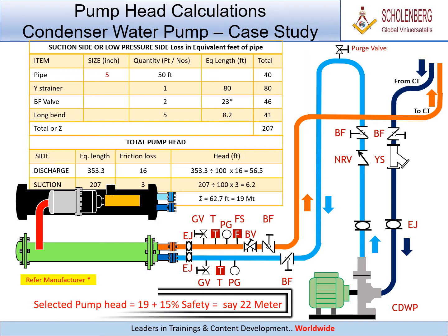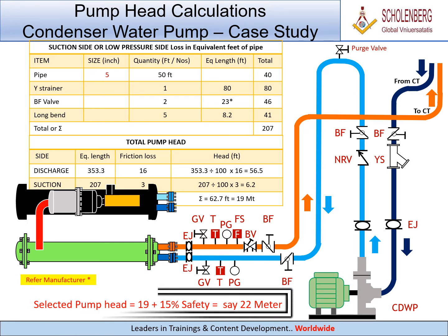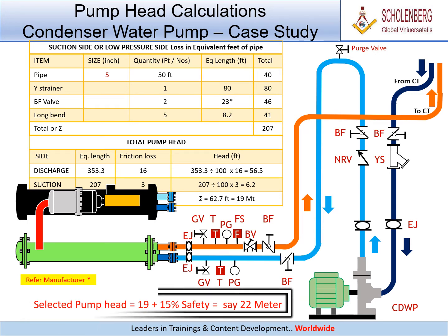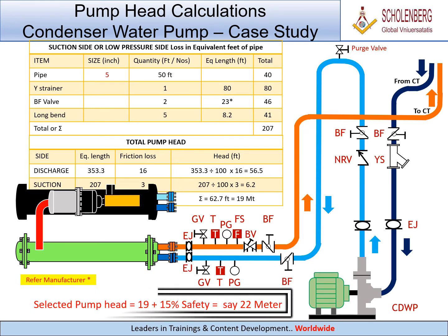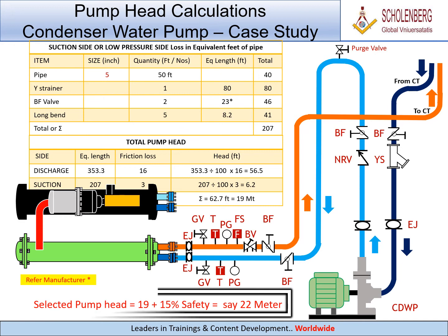Suction side or low pressure side loss in equivalent feet of pipe: total sigma equals 207 feet. Total pump head equals 19 meters. Selected pump head equals 22 meters.